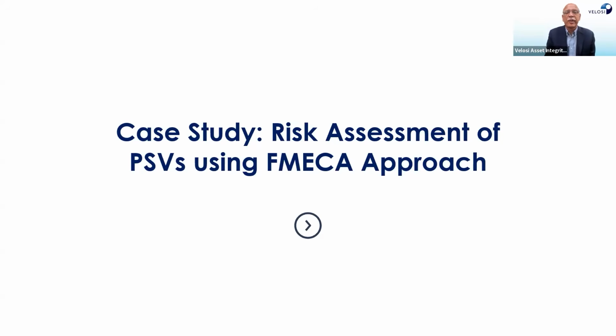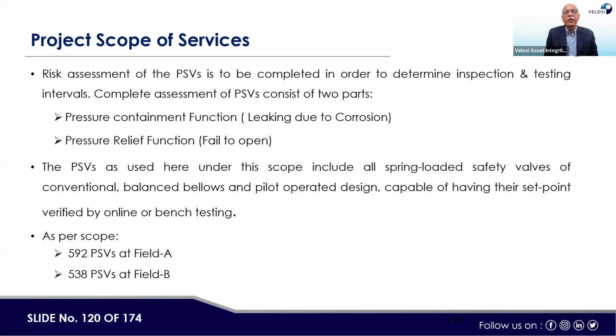Here, the project scope which was given to us: risk assessment of PSVs is to be completed in order to determine the inspection and testing interval. Complete assessment of PSVs consists of two parts: pressure containing function, leakage due to corrosion, and pressure relief function, failed to open. PSVs under the scope included all spring-loaded safety valves of the conventional, balanced bellows and pilot-operated design, capable of having their set point verified by online or bench testing.